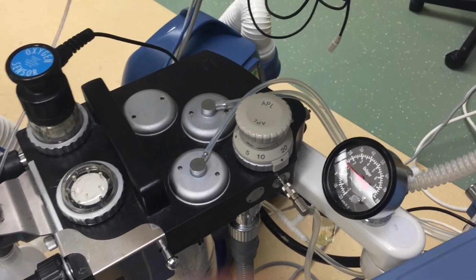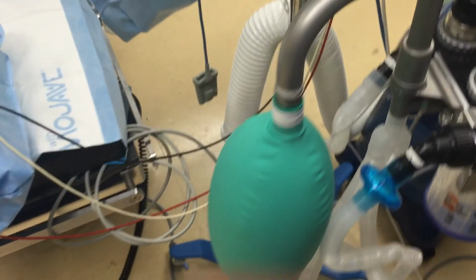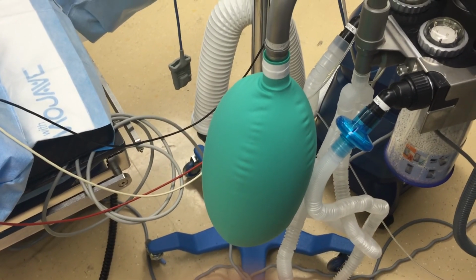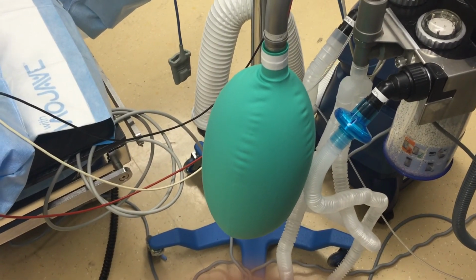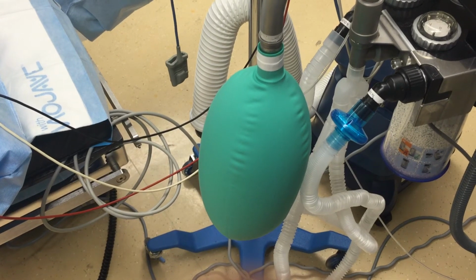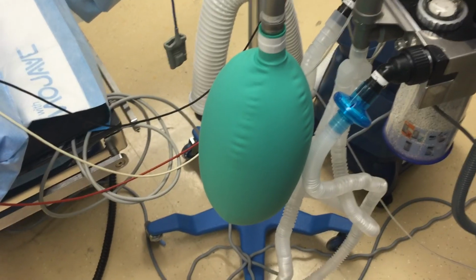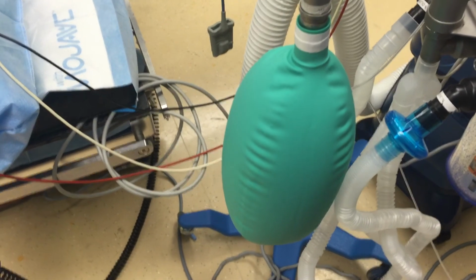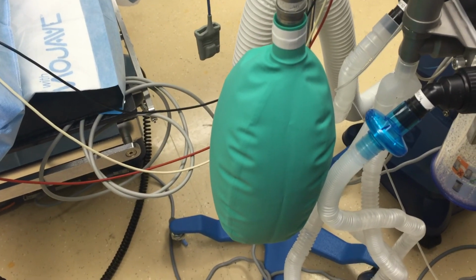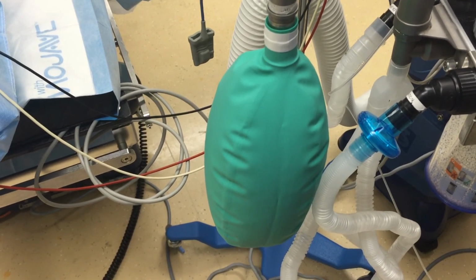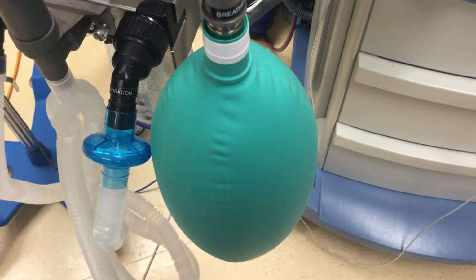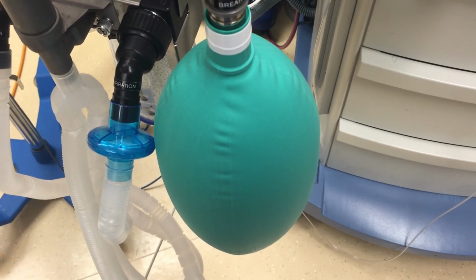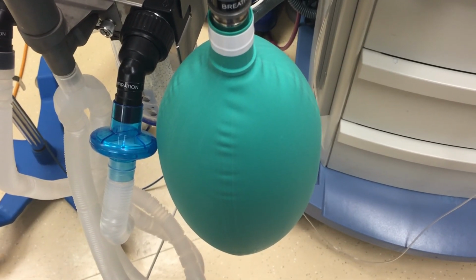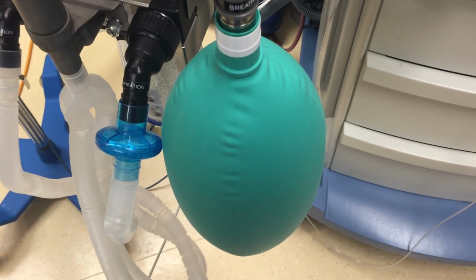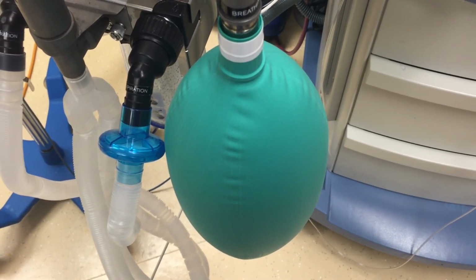From here, you want to make sure there are no leaks in the system. Tell the clinician to look at the anesthesia bag. The anesthesia bag should be inflated, as shown here. If it deflates, like this, that means there's a leak in the system, and you would want to check the seal around the SuperNO2VA. Next, you want to demonstrate to the clinician that the SuperNO2VA is providing effective, continuous positive airway pressure, or effective nasal CPAP.